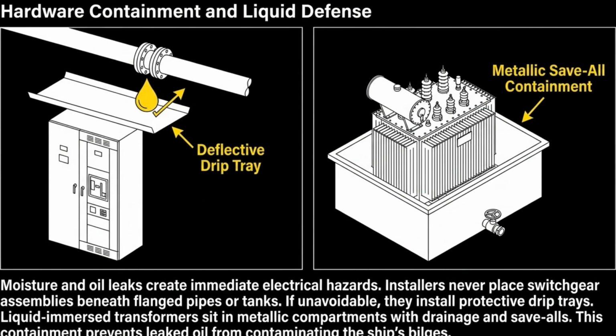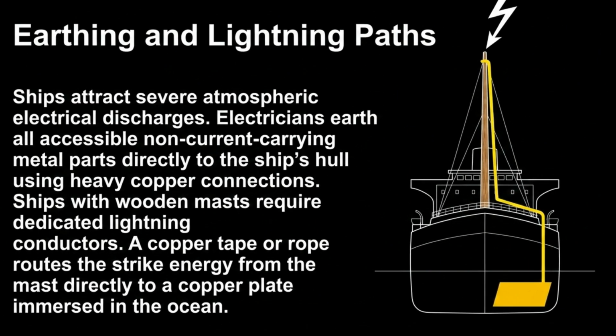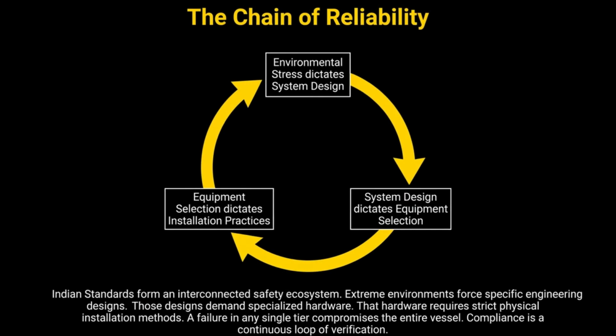To manage liquid hazards, switchgear must be protected from potential leaks. Protective drip trays and metallic containment trays with drainage help prevent oil contamination of the ship's bilges. Ships are susceptible to lightning strikes. Electricians ensure safety by earthing all non-current carrying metal parts and installing dedicated conductors to route strike energy safely into the ocean. The safety ecosystem is a continuous loop.